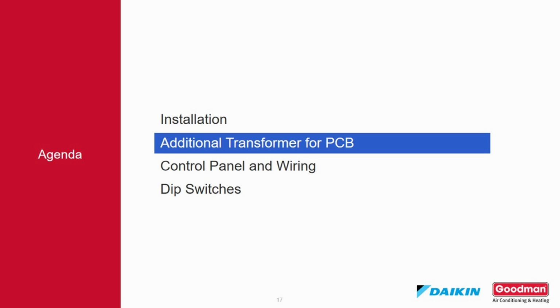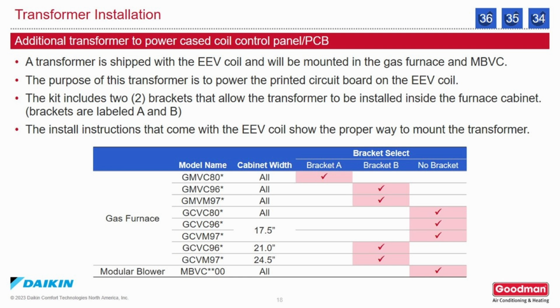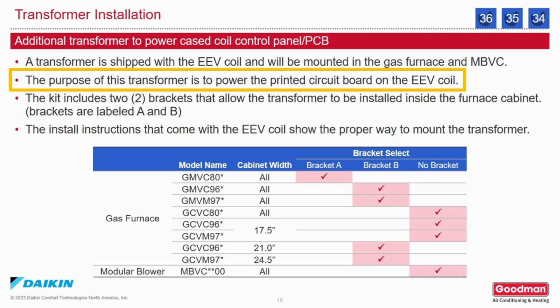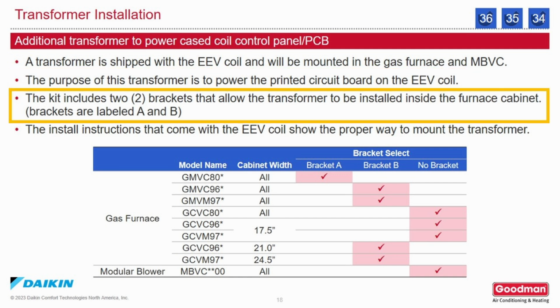Additional transformer for the printed circuit board. For adding an additional transformer to a power-cased coil control panel, a transformer is shipped with the EEV coil and will be mounted in the gas furnace and MBVC. The purpose of the transformer is to power the printed circuit board on the EEV coil. The kit includes two brackets that allow the transformer to be installed inside the furnace cabinet.